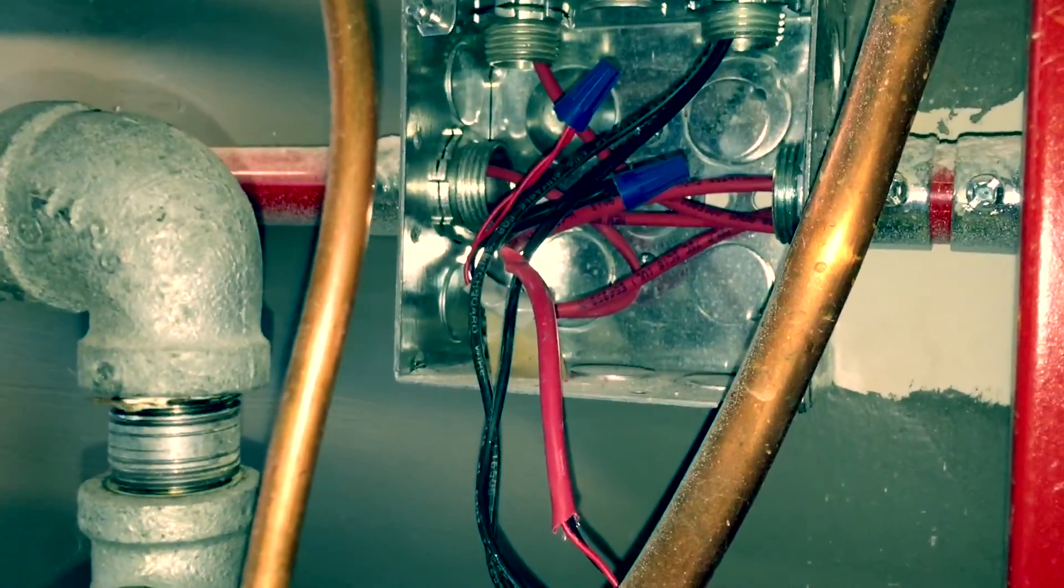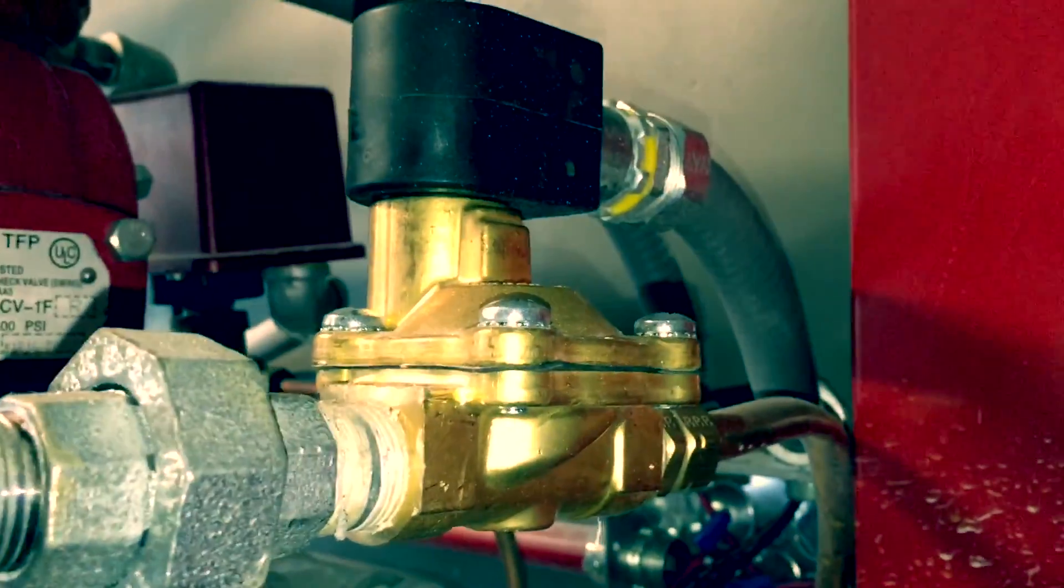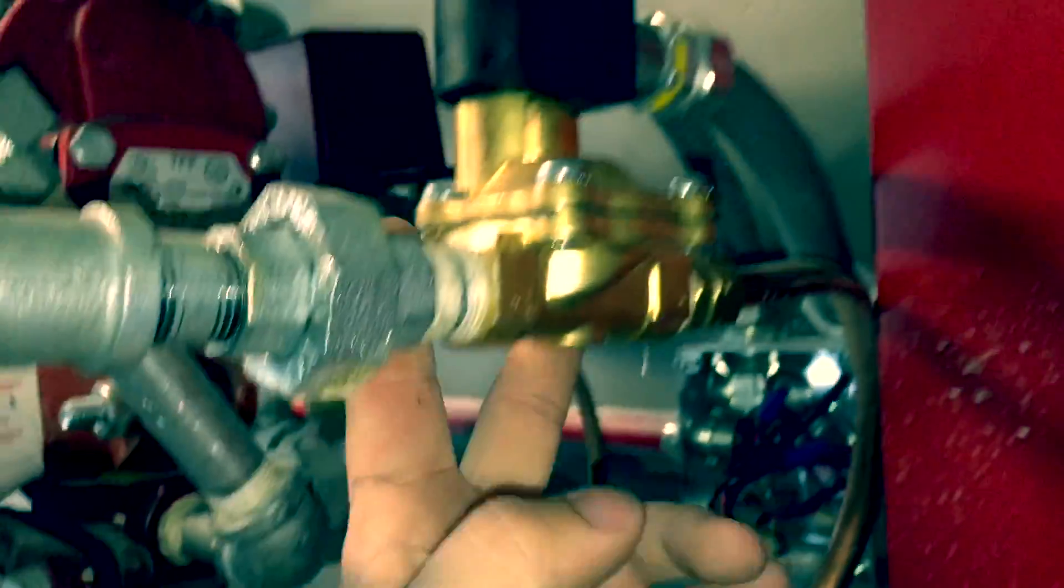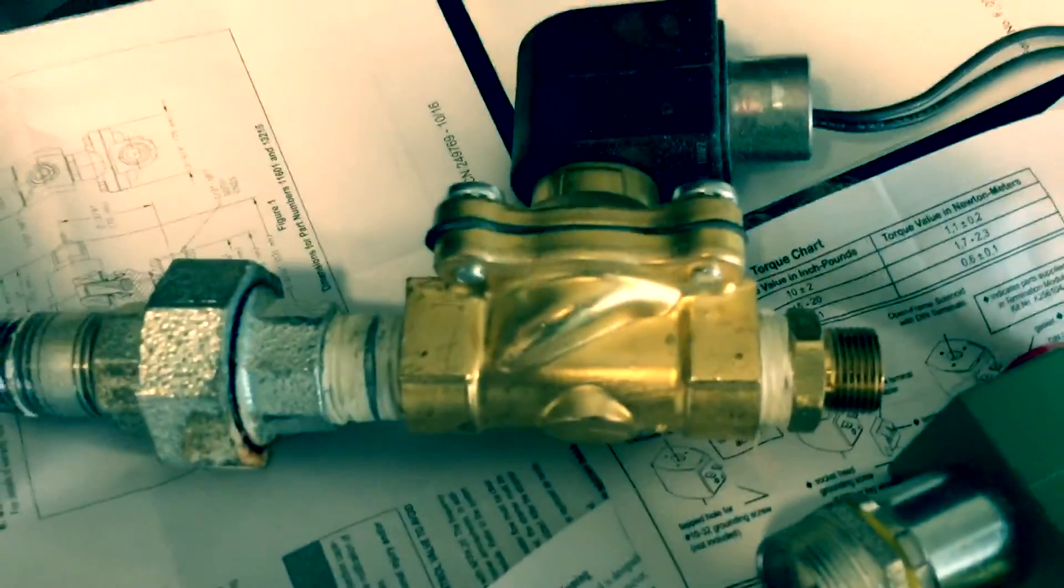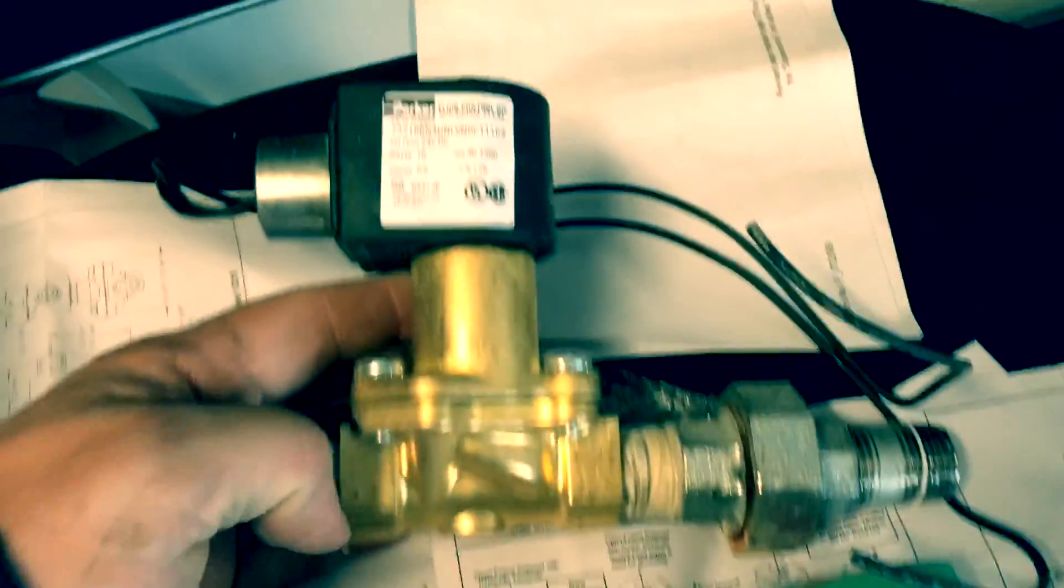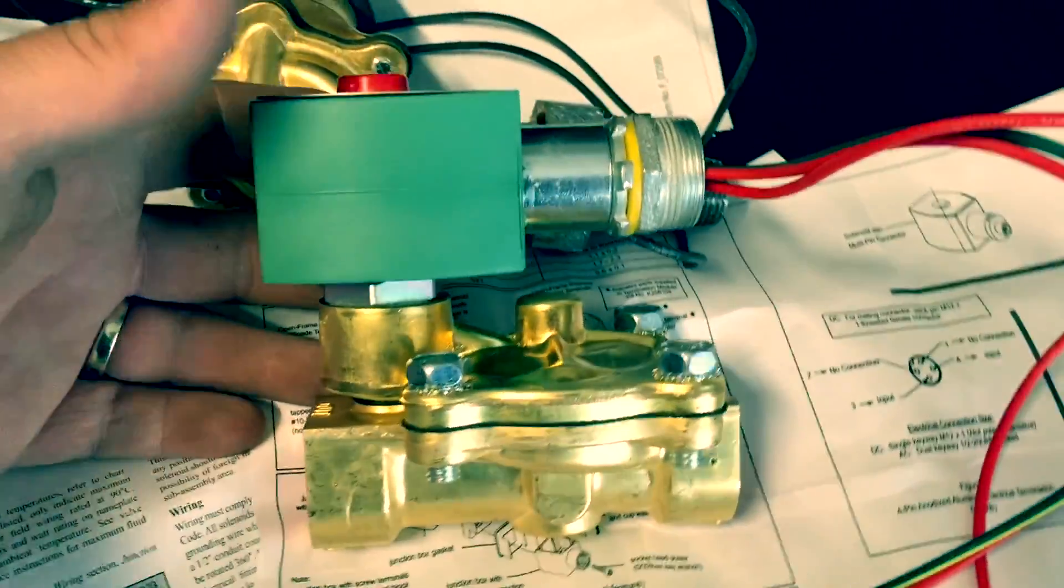We'll disconnect the electrical 24V to the solenoid actuator and then once we do that we will replace it and wire it back up and test it. Here's the old one, solenoid actuator came off the Tyco valve. Here's the new one that we're going to put on there. It's normally closed, when power is sent to it, it opens up.